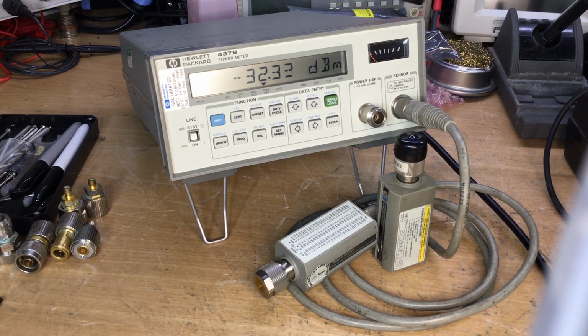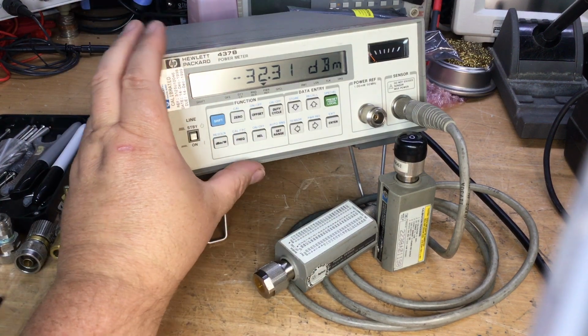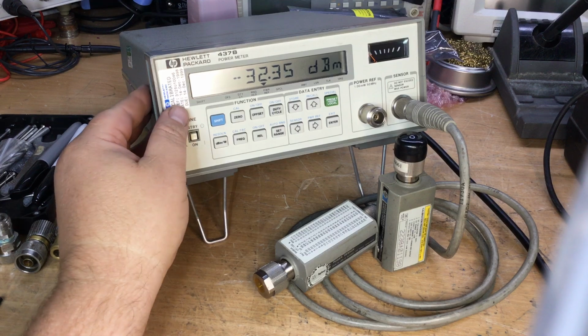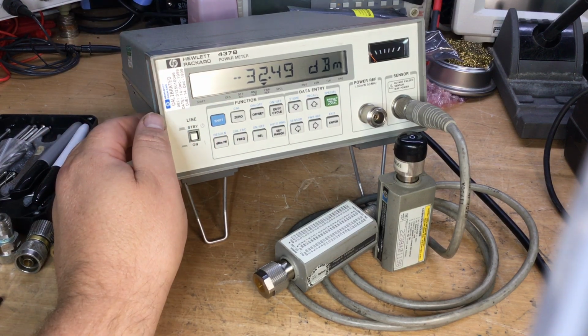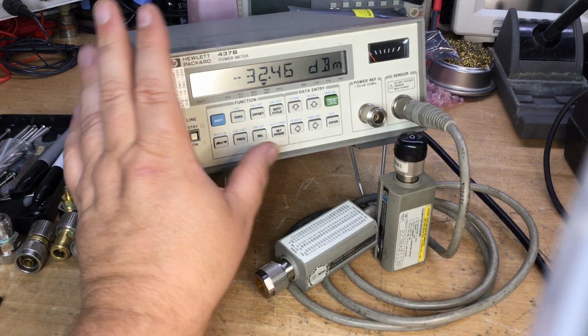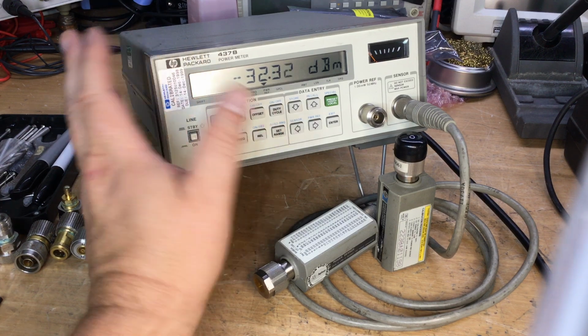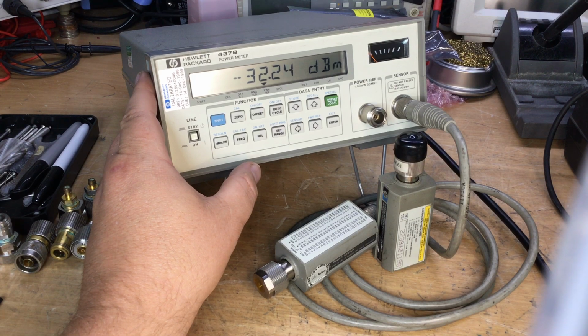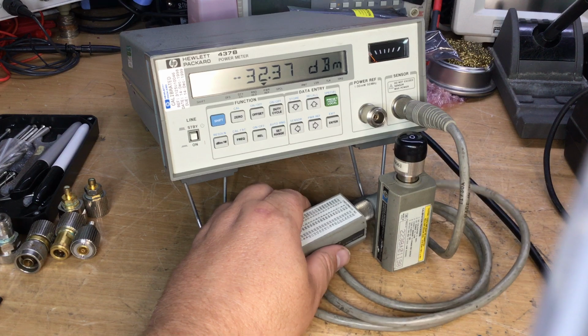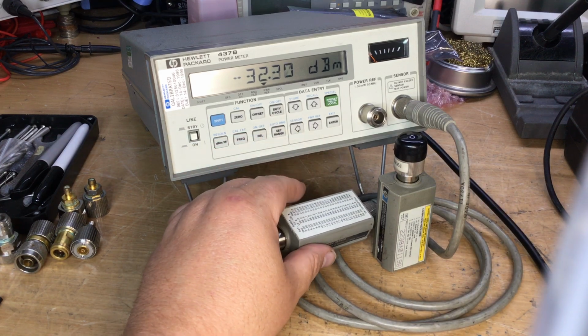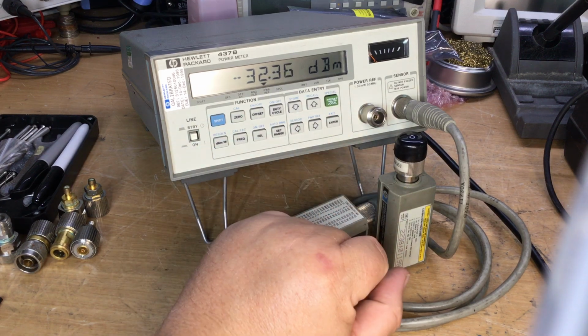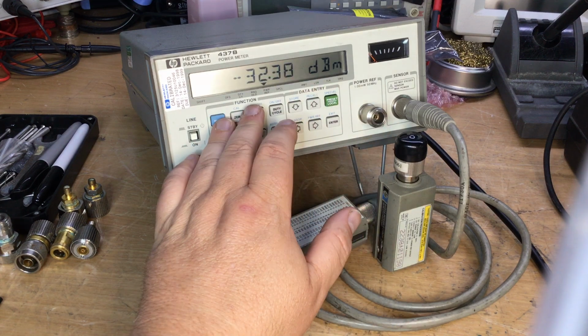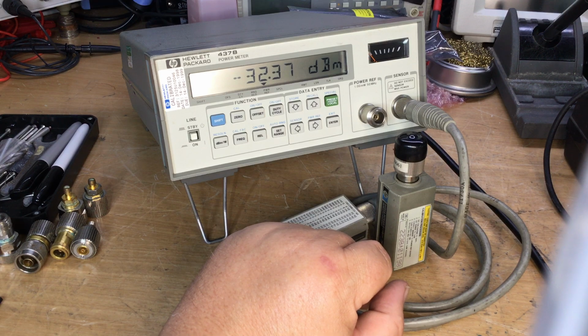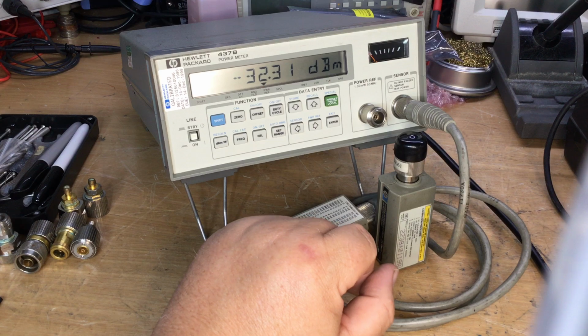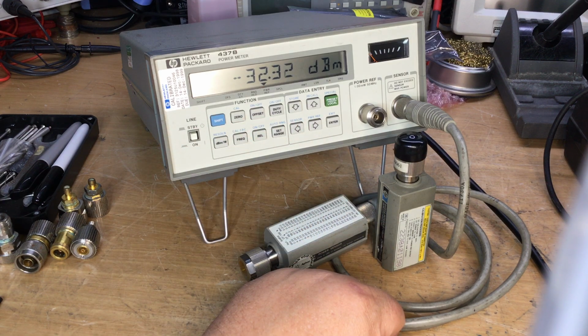Okay, so I think that's more or less the end now. I think we've done pretty well. We've calibrated the reference output on the meter. After 25 years it's been set up again, so my other friend will get this back now, all calibrated. So if he gets sensors for his meter, if he hasn't got them, at least he knows that it'll be calibrated. And the other friend of ours now will get one repaired sensor back, obviously, which wouldn't zero, and the other sensor worked fine without an issue, and we've verified both sensors on this meter as well as using the Marconi microwave test set on a sweep test up to 26.5 gigahertz. So obviously the sensors are good, so I'm sure our other friend will be very pleased about that.